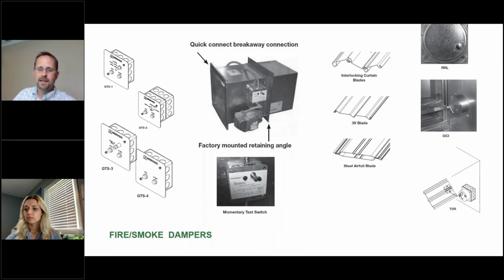These are things that you want to make sure you don't specify if they're not really needed for the project, because that's just cost to the owner that they don't need to spend. So make sure that you think through in your specifications where these are needed and that you identify which dampers need those options. And obviously these dampers need to be tested, and there are multiple options for manufacturers' test switches, and also through your fire alarm contractor.